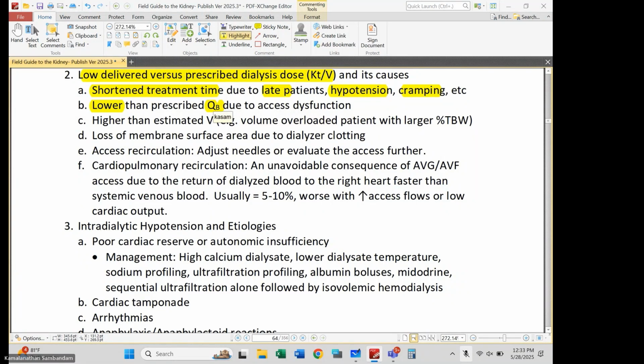So if I'm running 400 blood flow rate, I'm looking for access pressures either on my return side or my pull side. You want them less than 200, right? If I'm running 400 blood flow. Remember, again, that's with normal size needles. Don't get fooled if you're using 17 gauge needles. Everyone's going to have high access pressures. Okay. So access dysfunction, needle placement, those would be another cause of low blood flows.